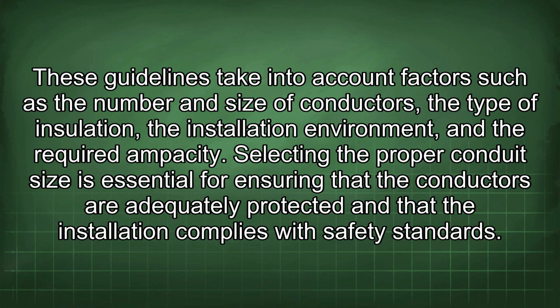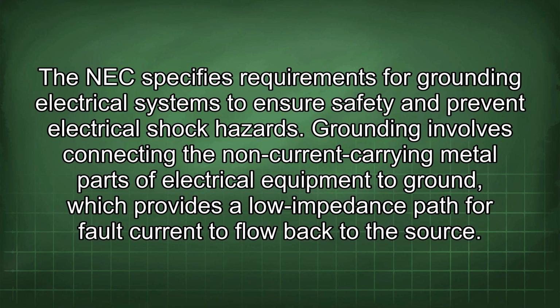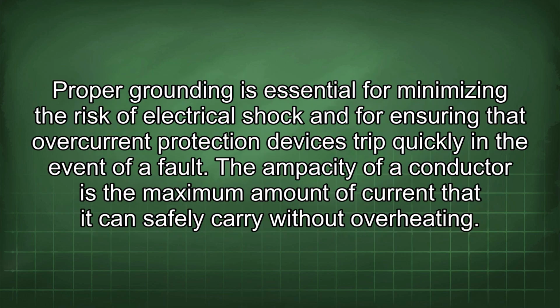Selecting the proper conduit size is essential for ensuring that the conductors are adequately protected and that the installation complies with safety standards. The NEC specifies requirements for grounding electrical systems to ensure safety and prevent electrical shock hazards. Grounding involves connecting the non-current carrying metal parts of electrical equipment to ground, which provides a low impedance path for fault current to flow back to the source. Proper grounding is essential for minimizing the risk of electrical shock and for ensuring that overcurrent protection devices trip quickly in the event of a fault.